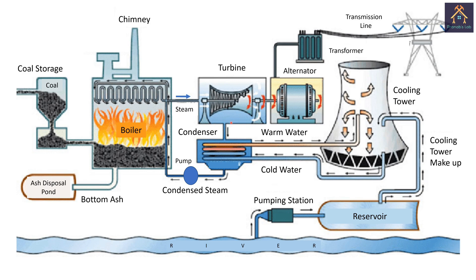The low pressure steam coming out from the turbine is condensed at the condenser and then converted into water and pumped into the boiler again. For cooling down the steam in the condenser, a continuous cold water is supplied. The heat of the condenser circuit is exchanged at the cooling tower. For make-up water at the cooling tower, water from a nearby river is pumped through the reservoir and fed to the cooling tower circuit. This process continues and runs throughout the year. A thermal power plant runs on a modified Rankine cycle.